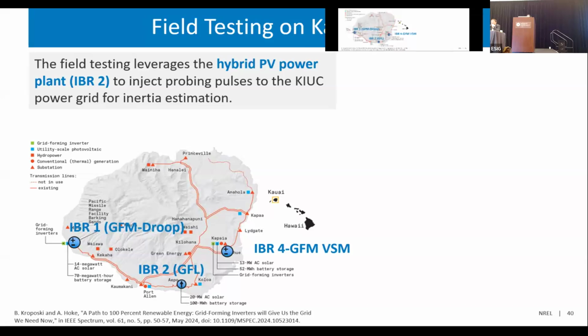In 2022, they converted the second grid-following inverter into a grid-forming unit, which is IBR1 on this map. So what we did here is work with our partner and implement the probing signals at the IBR2 site, injecting a 1.4 megawatt power pulse into the grid continuously.